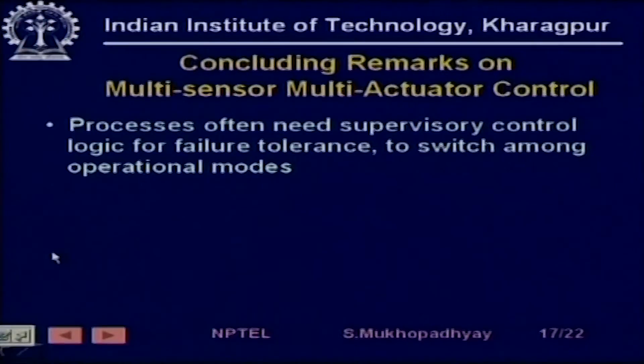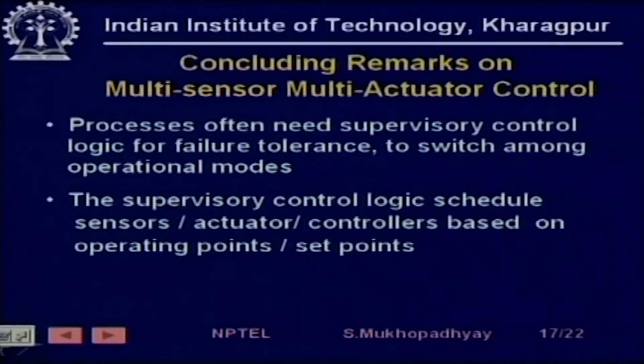We have come to the end of the lecture. Some concluding remarks on multi-sensor multi-actuator control: industrial processes often need supervisory control logic. Apart from the basic control logic in either the hot water valve or cold water valve, there will be an automatic controller. Above that you need logic based on process variables to determine which sensor will be active, which actuator will be active, and which controller will be active. This is called supervisory control logic, and it is needed for process operations. It is achieved through these control loops, which switch among operational modes and schedule sensors and actuators.